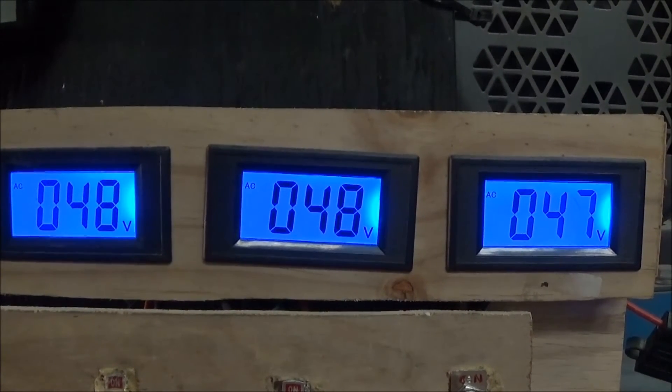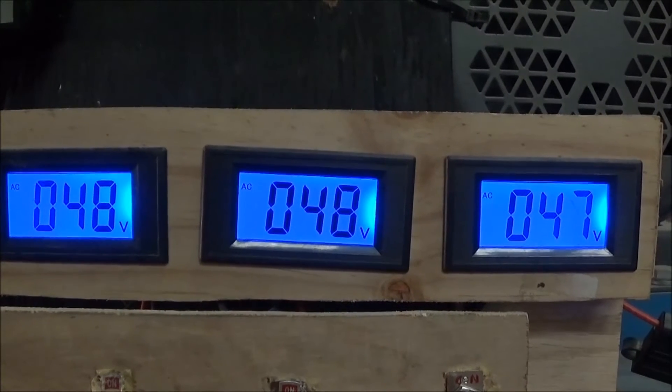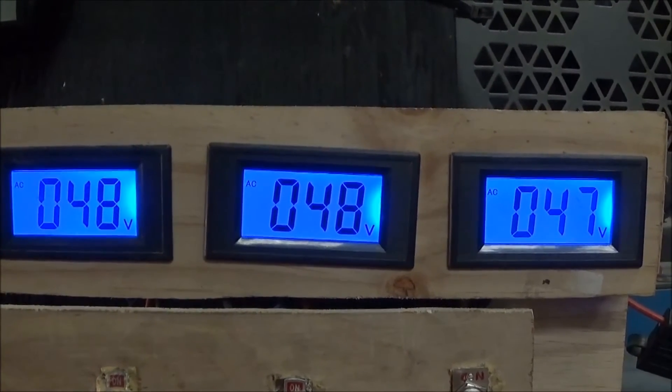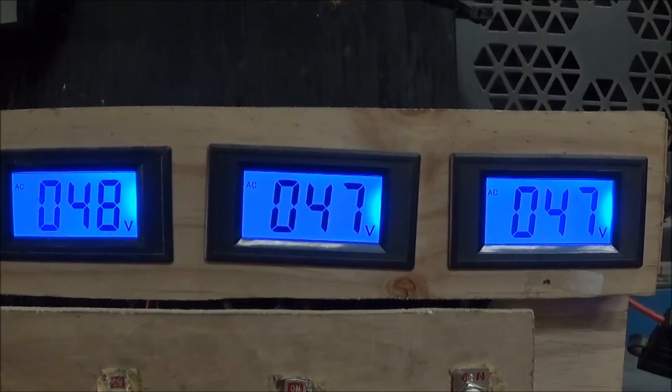We got 48, 47, 48. So all three of them are putting out, and they're within 5% of each other. So this stator is good.